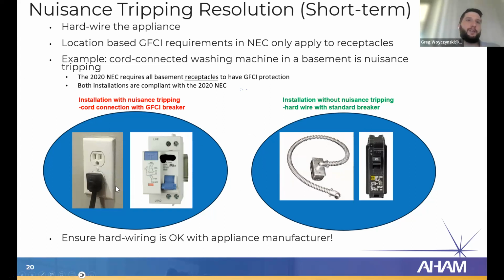So this may be an installation that you had nuisance tripping on, cord connection with a GFCI breaker. So the wires from this receptacle feed back through the walls into the breaker panel and come to a GFCI breaker. Well, that doesn't have to be the installation. There's another installation that the National Electrical Code allows, and that is hardwiring. So you can hardwire that washing machine into a junction box, and then that GFCI breaker can be replaced with a standard breaker. And that is completely allowed by the 2020 National Electrical Code.